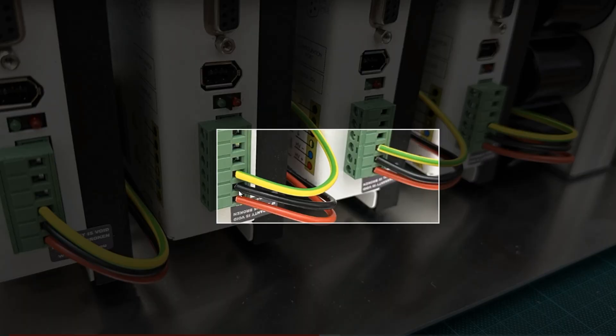And just remember, guys, any points of entry, any point where this is not insulated inside that terminal block—you can see a little copper there, a little copper there—that's over 300 volts of power going to each drive. That's how serious this is. It's not me being technical, it's me being critical of what you're working with. You do not want to make contact with that at all on your body. This is an industrial rated system. Each drive I believe is 750 watts. That's no joke, guys.